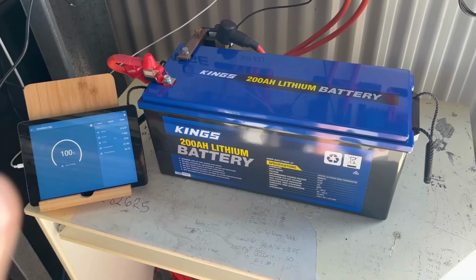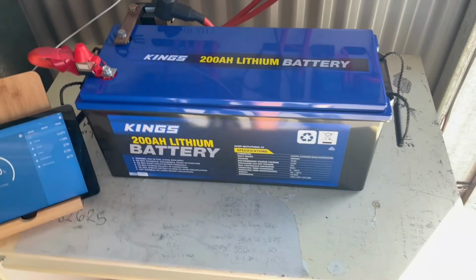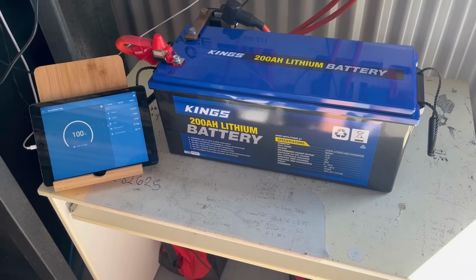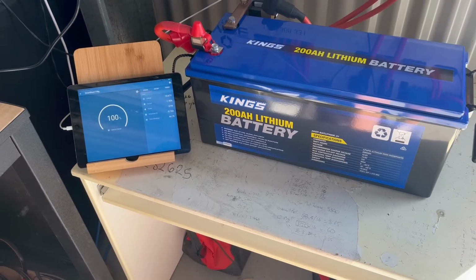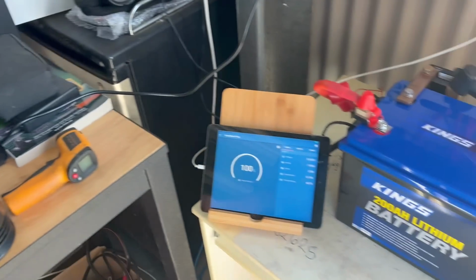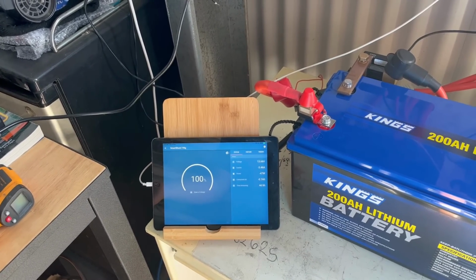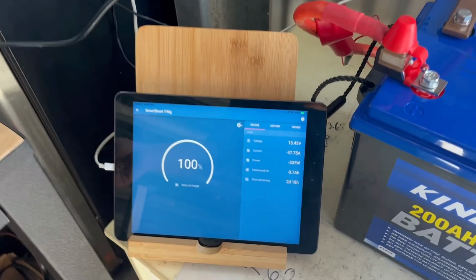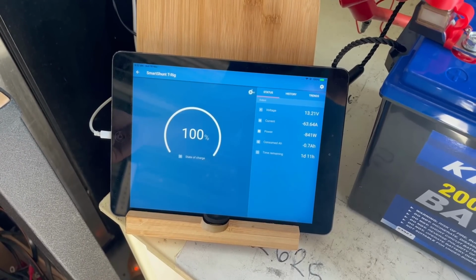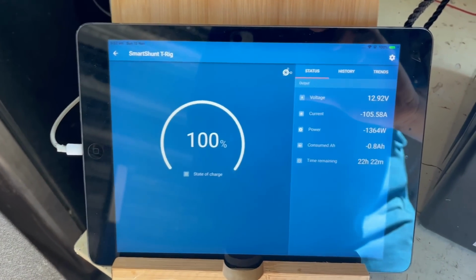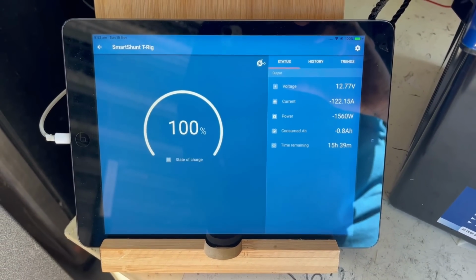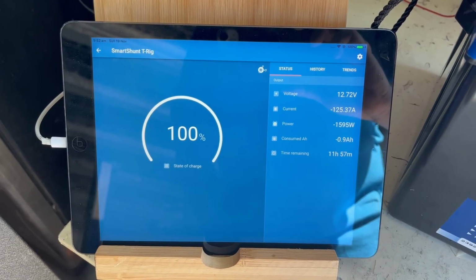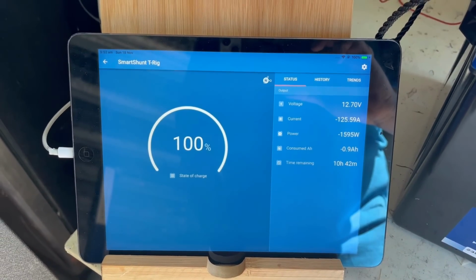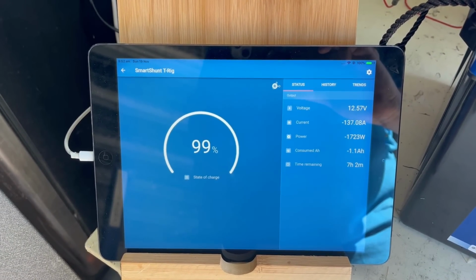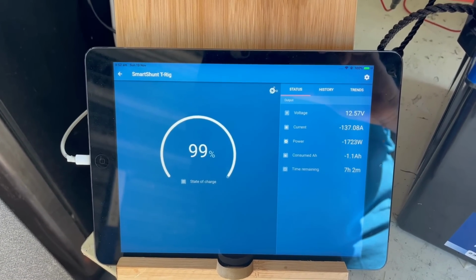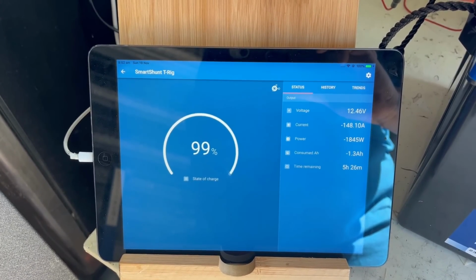Okay, so it's the next morning. I've let the King's 200 amp hour charge up overnight, and we'll do another discharge test on it today. Just the fan heater again is low, I'll turn that on now, and you'll see the amps come up. Just keep watching that for a second. 125 amps. Obviously the amps is going to rise as the voltage drops. There we go, 137 amps, 145 amps.